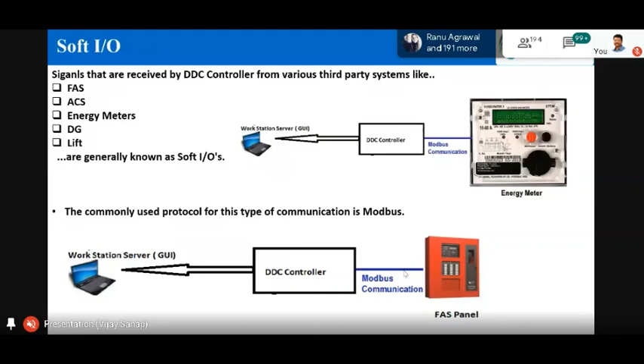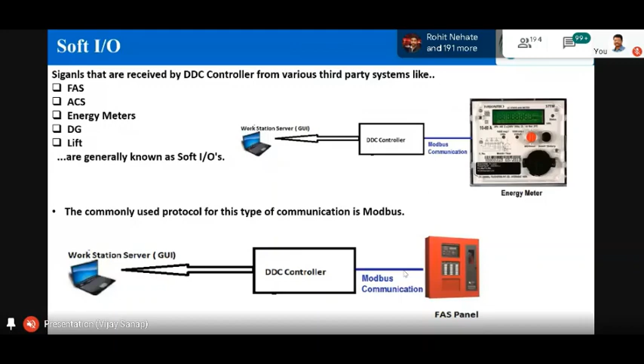You also have soft I/Os. So when you integrate, as I said earlier, Modbus is the interface which is majorly used for connecting third-party systems to BMS. Now, you can connect a fire alarm system to BMS, the fire alarm system connected to BMS on Modbus. So all the detectors of the fire alarm system, when they go inside BMS, they are like soft I/Os because they go on Modbus. Same is with access control systems. You have energy meters, you have DG sets, you have lifts. All these devices are connected over a Modbus interface. There is an option that you can also connect these devices through real I/Os, but then there is a limitation.